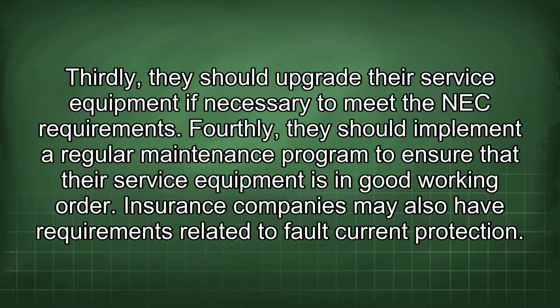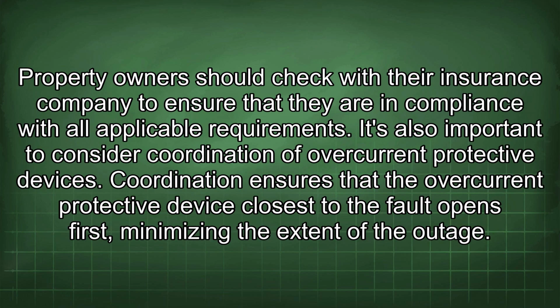Insurance companies may also have requirements related to fault current protection. Property owners should check with their insurance company to ensure that they are in compliance with all applicable requirements. It's also important to consider coordination of overcurrent protective devices. Coordination ensures that the overcurrent protective device closest to the fault opens first, minimizing the extent of the outage.